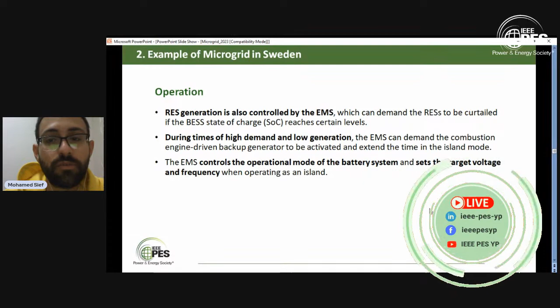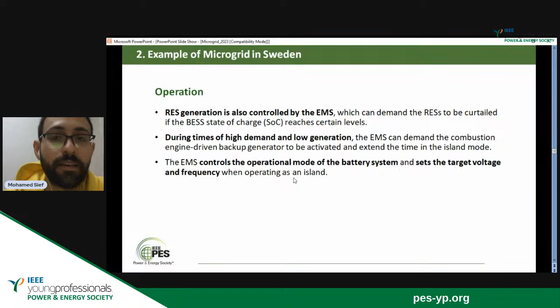During times of high demand and low generation, the energy management system can demand the combustion engine to operate in order to fulfill the needs of the customer, especially in the case of islanding mode. In the islanding mode, we are disconnected from the main grid, so we need to fulfill the requirements of our customers in the first place. And of course, you will have main regulations like a specific voltage level and a specific frequency level, in order to avoid any harmful effect to the appliances or any devices at homes, factories, or offices also. The energy management system controls the operational mode of the battery system and sets the target voltage and target frequency, as we mentioned, especially when we operate in the islanding mode.